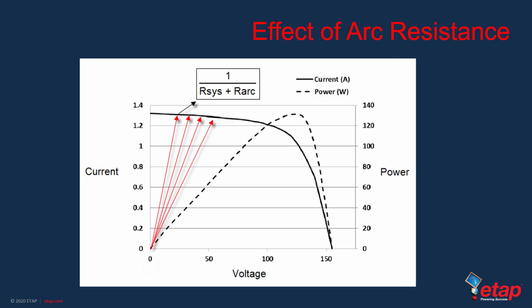The simulation results presented at the Electrical Safety Workshop in 2015 showed that it was very likely that the arc voltage was going to lie, in the majority of cases, or settle at a relatively low voltage portion of the IV curves of the panel. Consistently, in the model simulation results that I observed from the method that I developed, we saw that the arc voltage was about 30 to 40% of the maximum power point voltage. The resistance of the cables and connectors along the way is almost negligible, but is still considered.